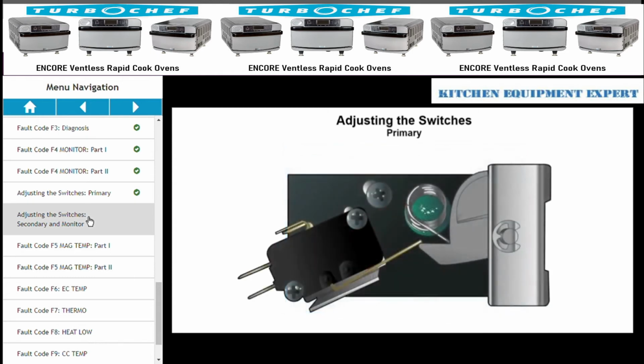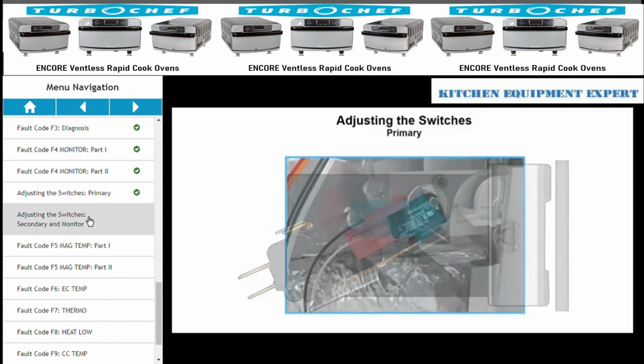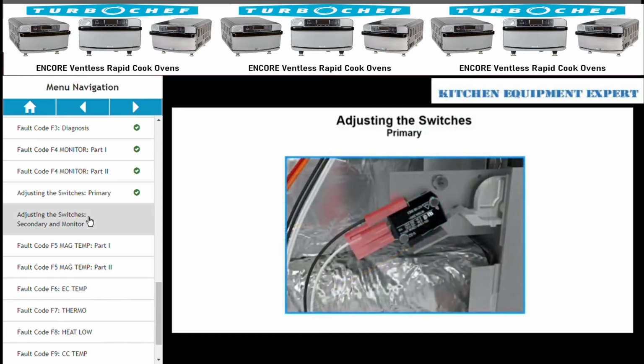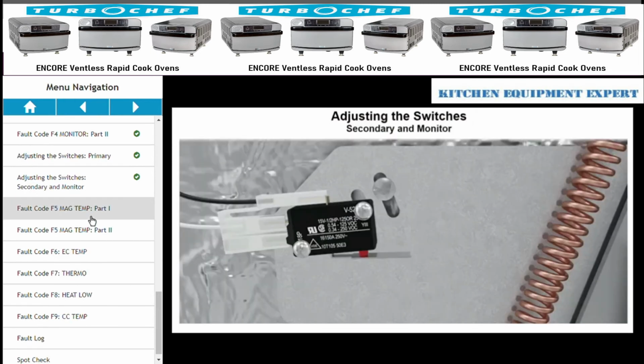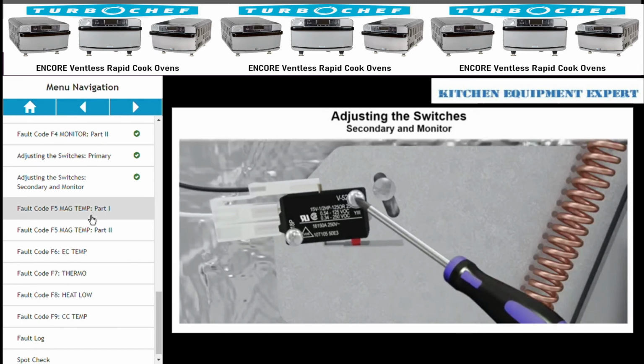Adding or removing shims between the assembly and the oven will move the switch assembly closer or further away from the door, and will decrease or increase the angle of the toggle. Adding shims will reduce the angle and removing shims will increase the angle. To adjust the secondary and primary switches, loosen their mounting screws and move the switch bodies until the primary switch disengages just before the secondary switch when the door is opened.